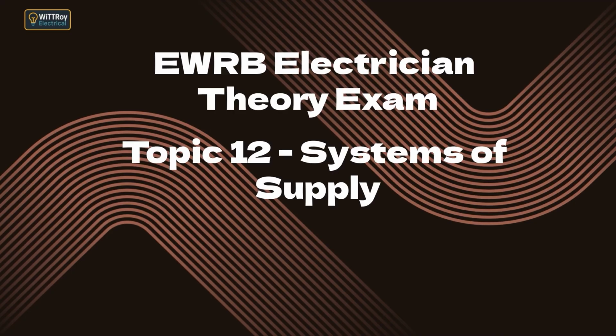12.1c. Draw and label the New Zealand three-phase four-wire distribution systems supplying a three-phase consumer, two-phase consumer, and single-phase consumer. New Zealand uses a three-phase four-wire system consisting of three-phase conductors and one neutral. A three-phase consumer receives all three phases and the neutral, giving them 400-volt phase-to-phase and 230-volt phase-to-neutral connections.